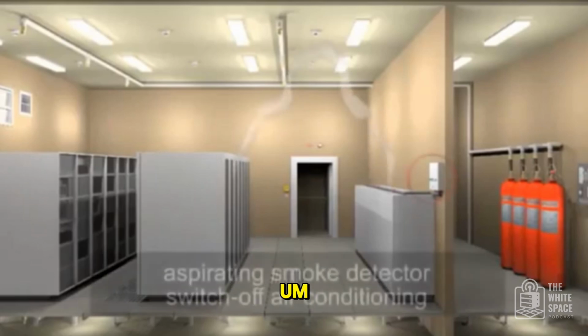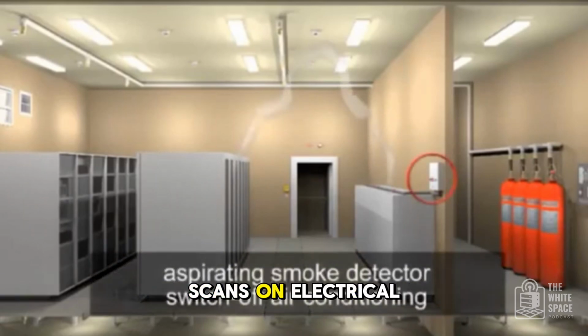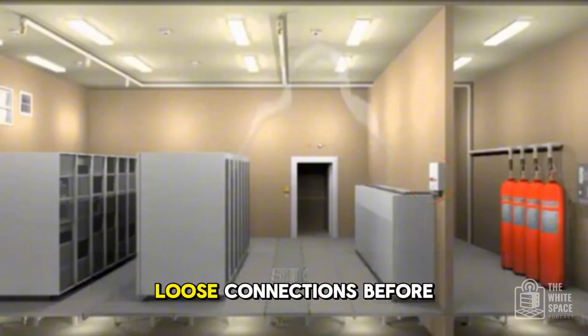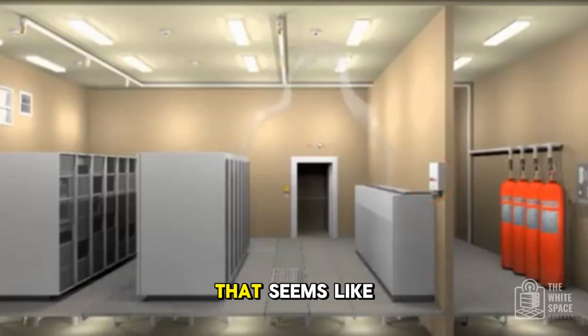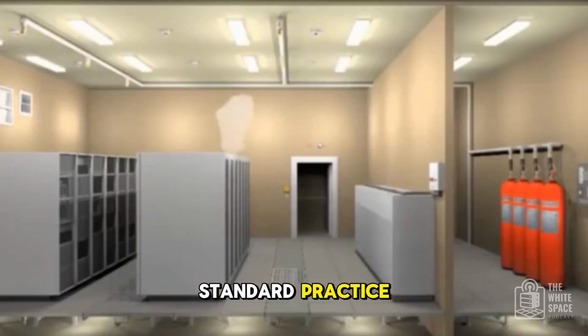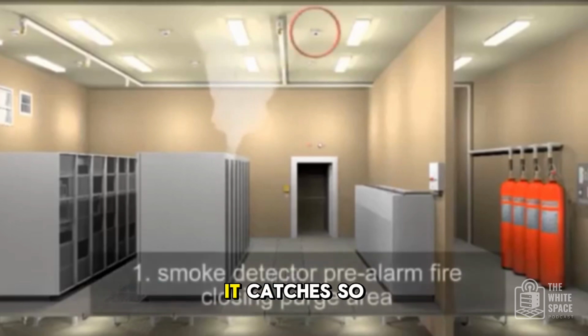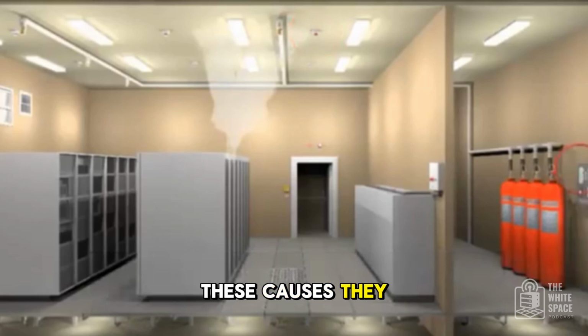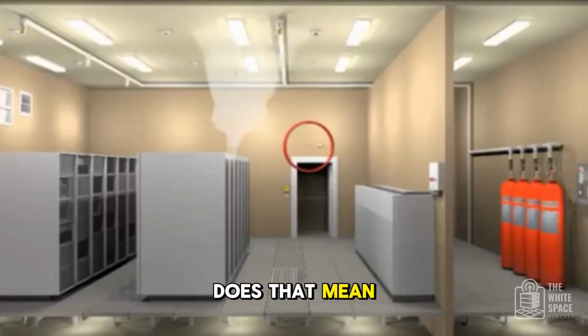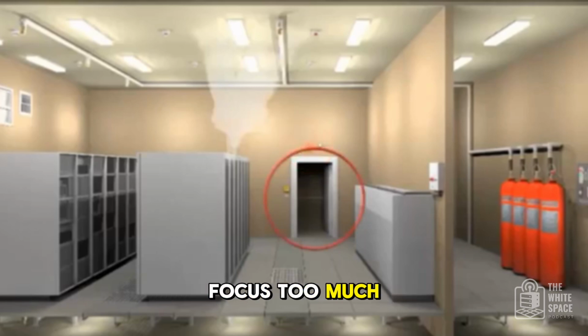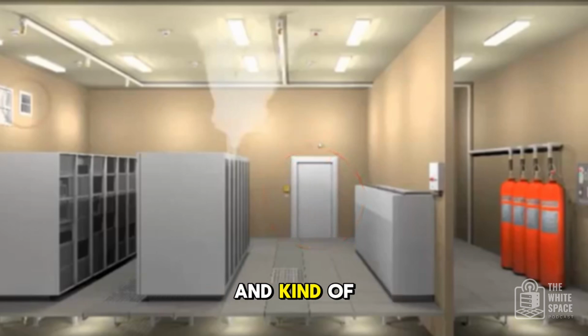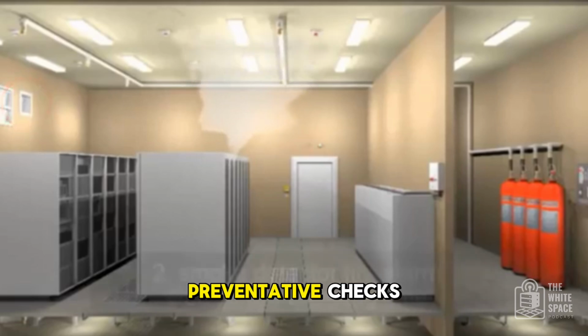So things like doing regular infrared scans on electrical panels to spot those hot, loose connections before they arc seems like a no-brainer. It should be standard practice, definitely. At least yearly. It catches so many potential issues. It makes you wonder, though. These causes sound quite fundamental. A loose wire, a forgotten box. Does that mean maybe some organizations focus too much on the fancy suppression tech and underinvest in basic housekeeping and preventative checks?